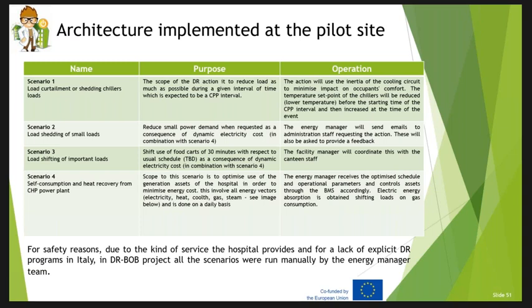Scenario 4 involves the new power plant, the tri-generation. The CHP provides both cooling and heating capacity to the hospital, and the heat recovered by the engine can be used in an absorption chiller or directly with a heat exchanger to warm up the hospital. In case of an event, we can switch all the warm capacity of the CHP to the absorption chiller, so we reduce the electric energy consumed by the chillers. So basically in this scenario we switch from a use of electric energy to a use of district heating or natural gas.